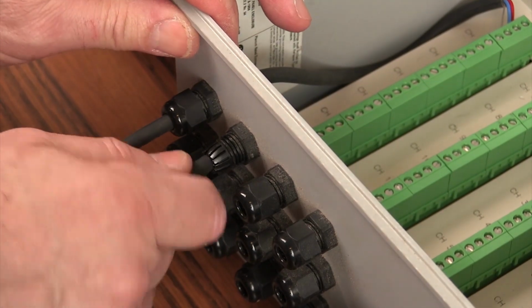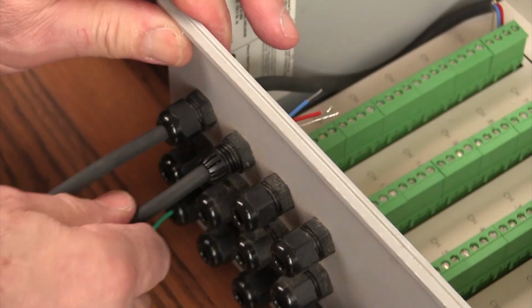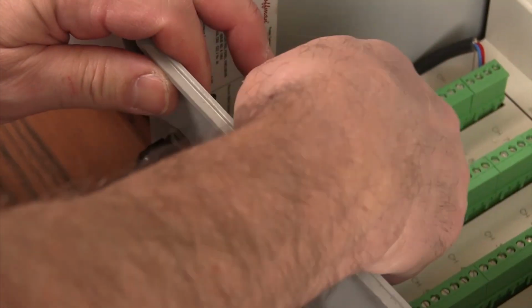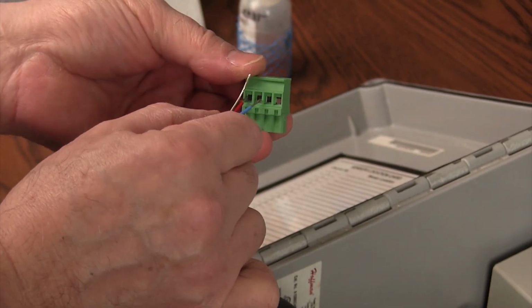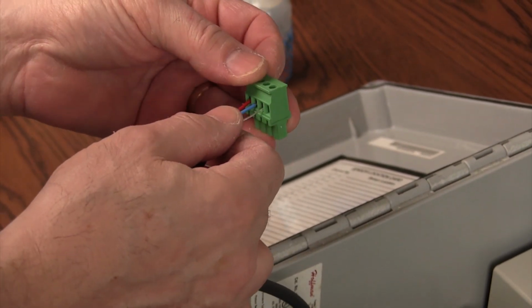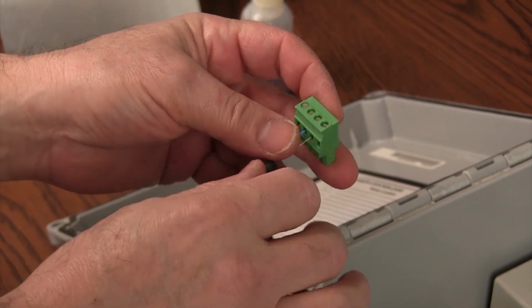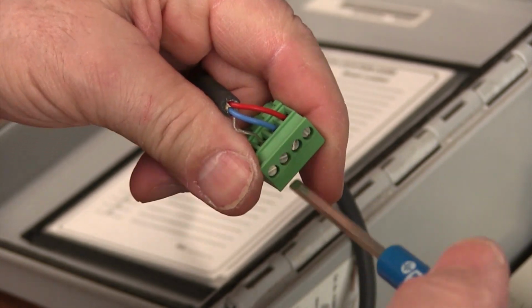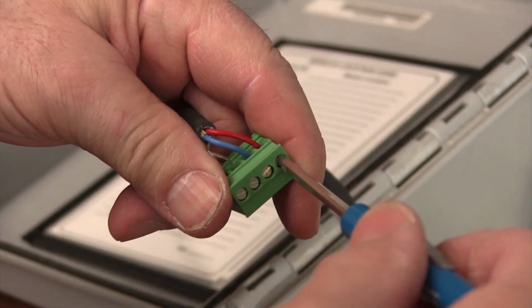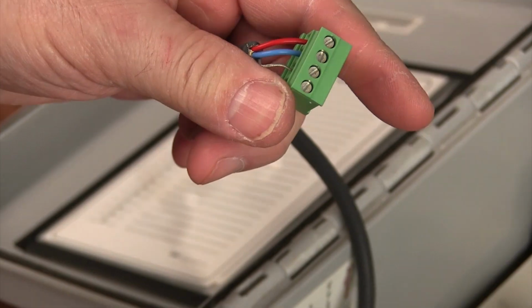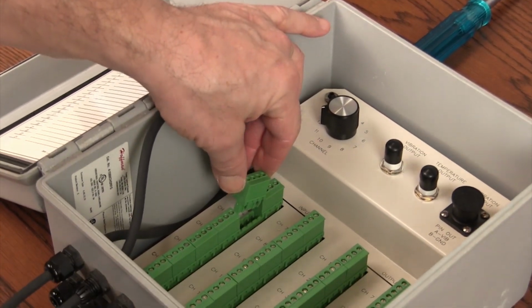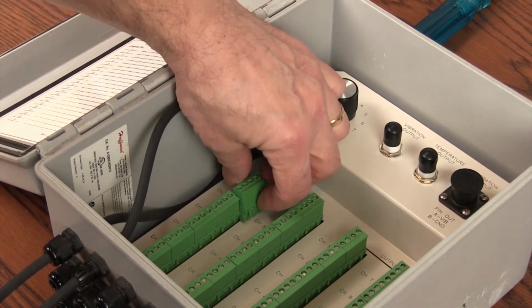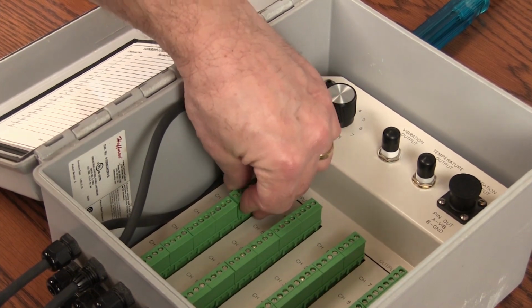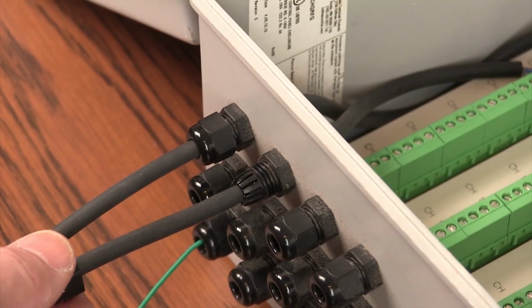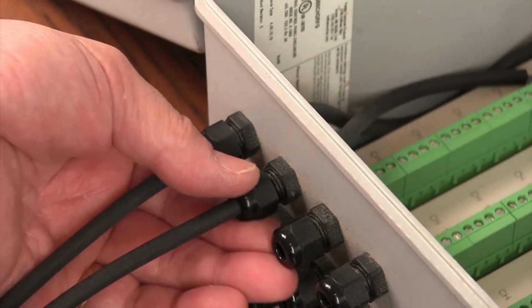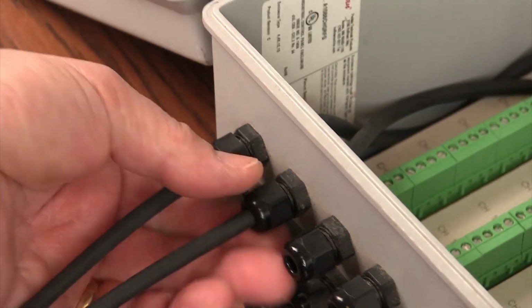We repeat the process for channel 2. Again, it's very important to connect the shield's drain wire. All of the drain wires are routed to the grounding lug at the bottom left of the box, which should itself be connected to earth ground during the installation. Snap the terminal strip back into place for channel 2. And retighten the nut on the back side of the cord grip.